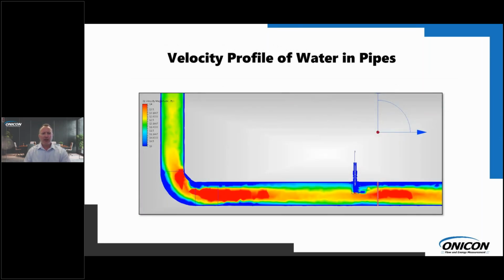Next, we have some CFD modeling, just showing you some of that turbulence that we're talking about after a 90-degree bend. So this is an example there on the screen. If you notice there, it's our insertion electromagnetic meter installed. And considering that insertion meter, you're only in a small portion of that pipe. So we're usually in the upper 1/3 or bottom 2/3. So obviously you don't want to be too close to the pipe wall because of the friction. So that's why it's so critical to achieve those accuracies.